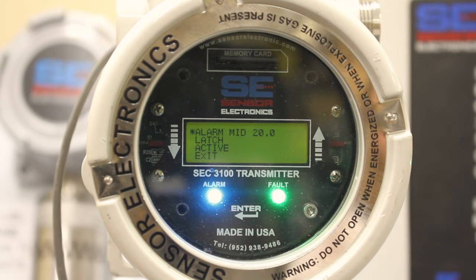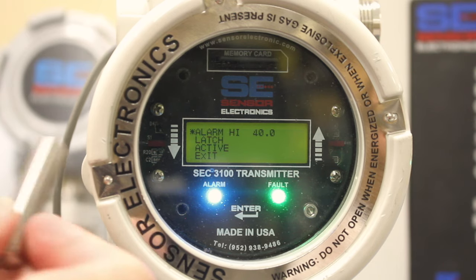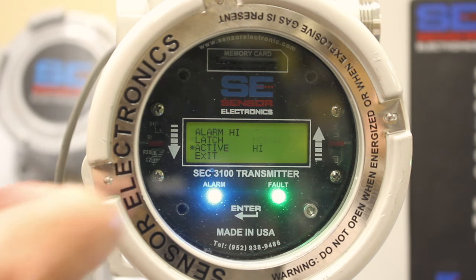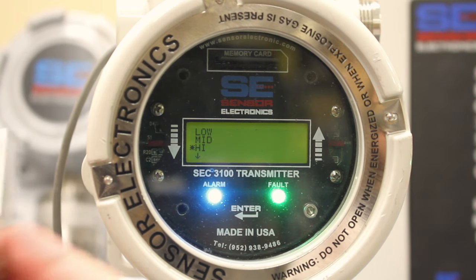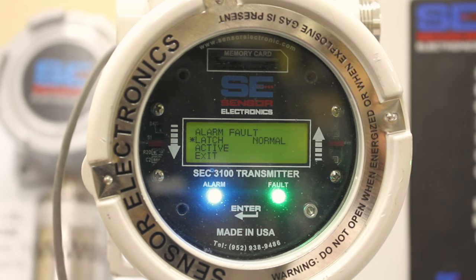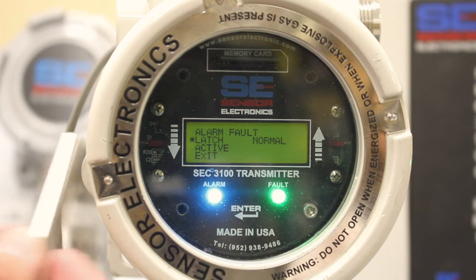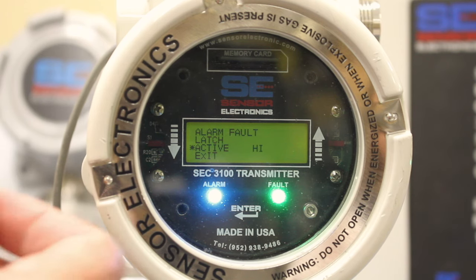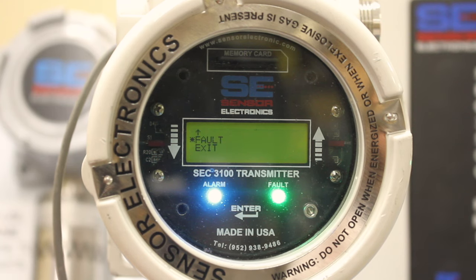It's the same setup, but you can see how they're programmed. And you can change these set points. And then the last relay we have is a fault relay, and you have the same type of things, except we don't have an alarm level. A fault is a fault or a not fault, so we can sequence through and you have the same active high, active low, and Exit. And then once you've made your changes, you can just arrow down to Exit.